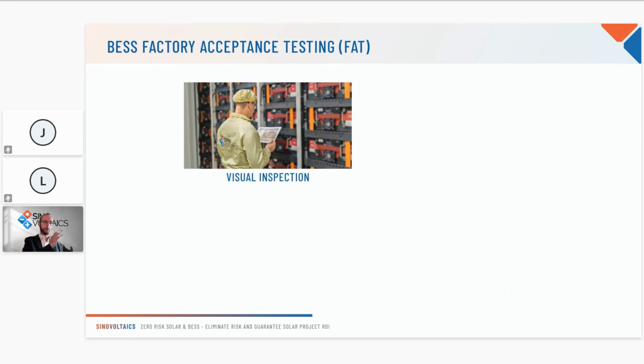First, FAT should be better understood, because it's really composed of 4 key points. First being visual inspection - not only of the container, but also the cooling system, the battery pack, the racks, making sure there is no scratches, damages, or rust. It's really, really key here.